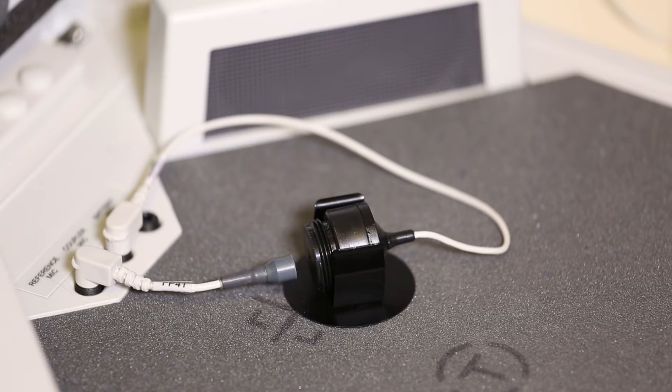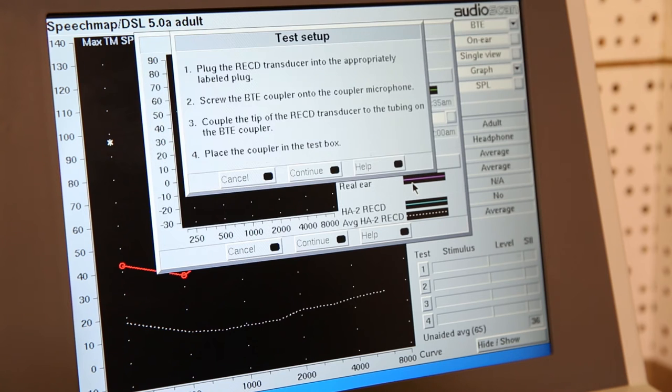Later, you may need to do the same thing with the reference and actual test microphones on the left and right ear probe attachments, if you are prompted to do so on the screen. Once calibration is complete, you may continue with RECD testing.